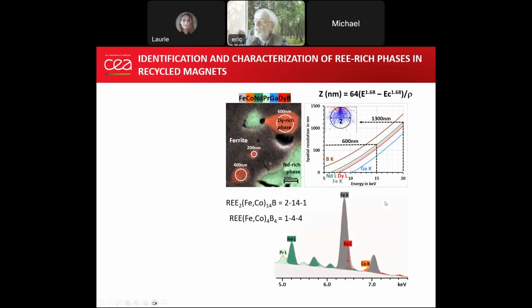And in general, it is in this region that we measure the rare earth elements, as well as iron and other elements, because in general, in that region, the X-rays are relatively well separated. This is not always the case, as shown here on this figure, because you see that you have strong overlap between dysprosium and iron, for instance, so it is so far difficult to measure low concentrations of dysprosium inside this sample. And we have the same problem with cobalt, which also overlaps with the K-beta line of iron.